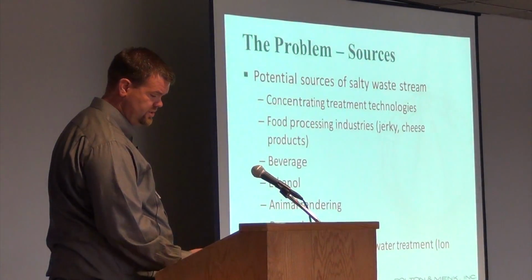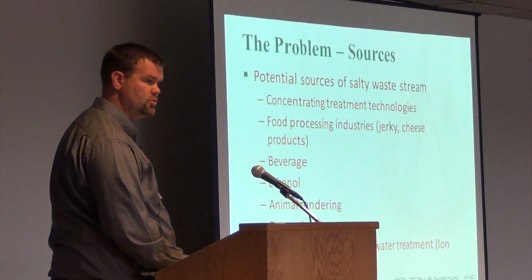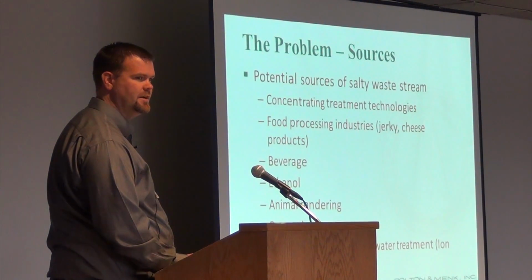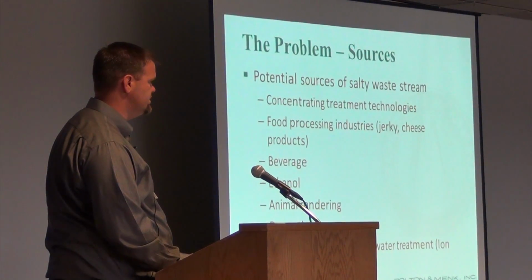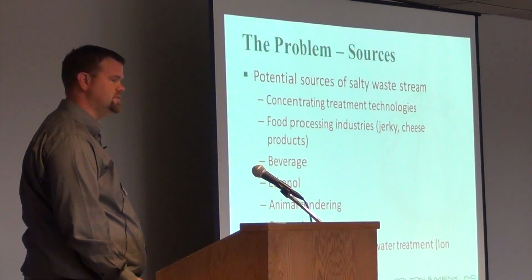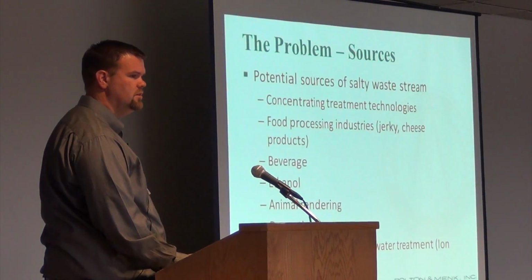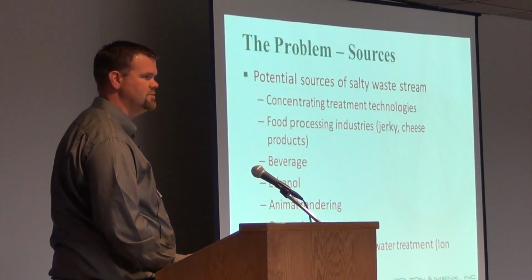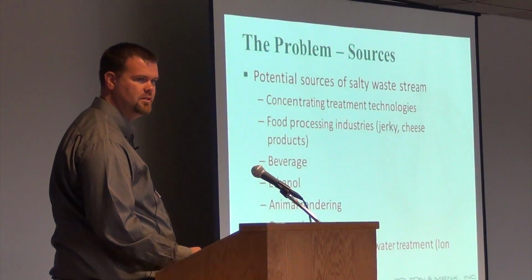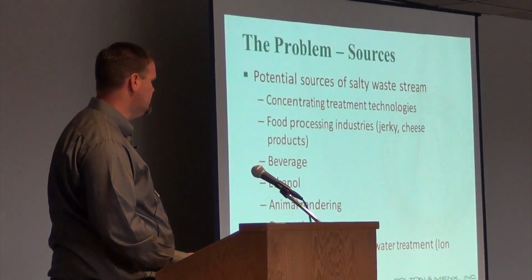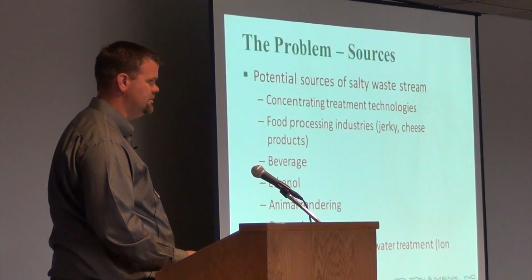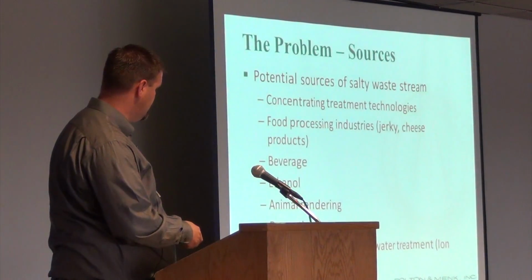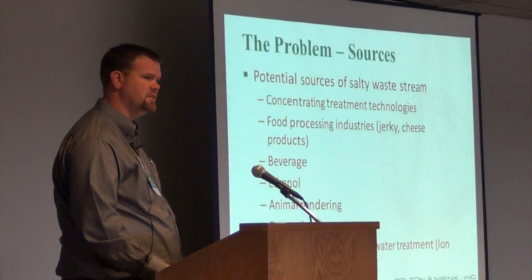There are concentrated treatment technologies, such as cooling water blowdown, where the water evaporates, the pure water, but the salts are left behind, and when that's discharged to wastewater, that increases the salt. There's food processing, where they're actually using salt in the process, such as beverage and ethanol. I was just talking to the City of Morris, and they've got an ethanol plant with 12,000 to 17,000 milligrams per liter of dissolved solids, so lots of solids in their waste stream. Animal rendering, domestic sources, human waste has got salts in it. We're taking in salts and discharging salts. And the big one that I'm going to focus on is the industrial and residential water treatment, and specifically that ion exchange.